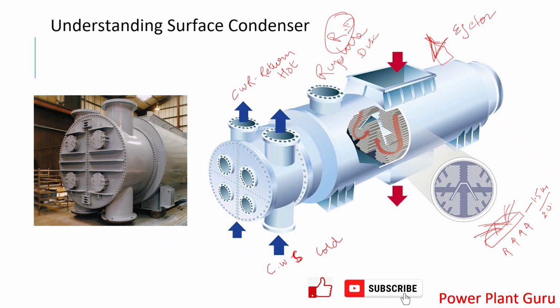So it is a protection because the equipment is designed to operate at a low pressure setting. And if there is some problem, maybe your cooling water supply is blocked, the pumps are tripped, and you are not able to maintain cooling water flow, then pressure will increase. There are other chances too, like the water which is going to the hot well and then to the condensate extraction system through pumping. If the pump trips or something else happens, then also it may cause high pressure. So for protection from that, the RD is there.